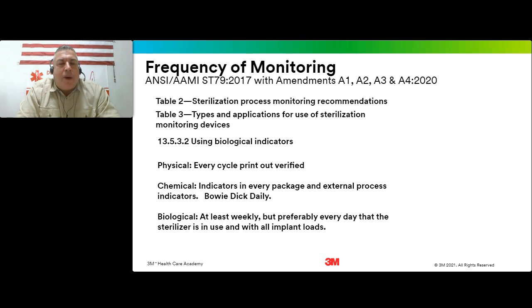That is pretty much a given. Now let's talk about that briefly, because some departments are able to write a policy for when the sterilizer is in use. So if they say daily, but you go into the weekend and you're only using one sterilizer out of three, or maybe you close on a Sunday, you don't have to send somebody in there to start the autoclave and do the testing. Make sure that's outlined in your policies.